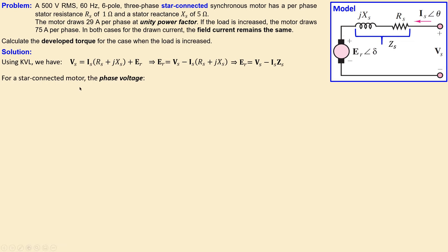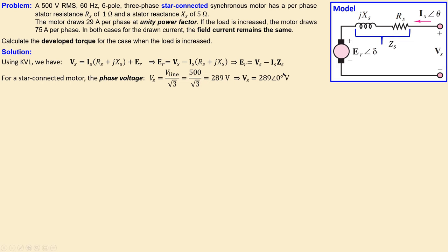For a star-connected motor, the phase voltage is found by dividing the line voltage by the square root of three: 500 volts RMS divided by √3 gives 289 volts RMS. Converting to polar notation, the phase is zero degrees because we take the phase voltage as our reference.